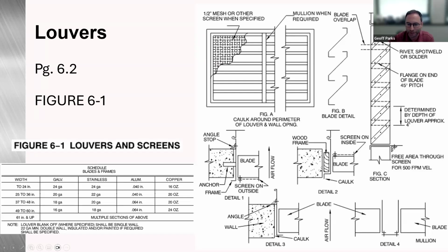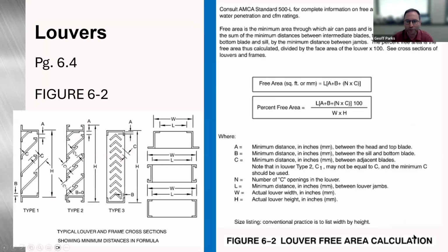I know there's a lot happening on this screen, so I'm not going to cover every single detail, but it gives you sill details, the mullions, and all that good stuff. Figure 6-2, this is on page 6.4. Here is where you can calculate the louver free area, based on the free area calculation dependent on the type of louver you're going to use, the types we have covered here, Type 1, Type 2, Type 3, depending on the frame and so forth. There's some useful information here to calculate that louver free area that I don't know a lot of people realize is in the Duct Construction Standards.